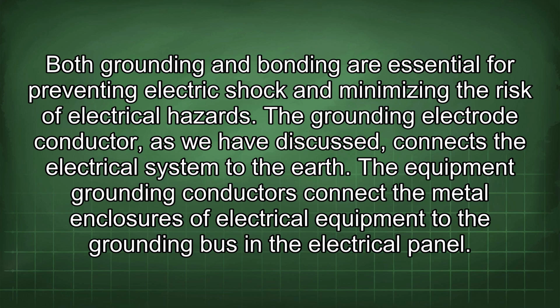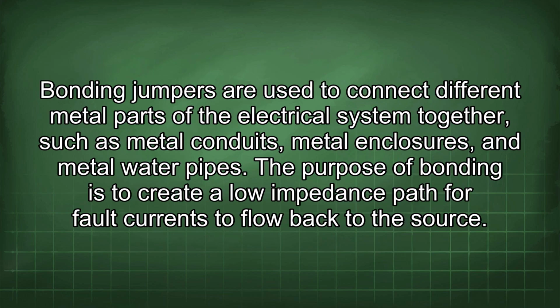The grounding electrode conductor, as we have discussed, connects the electrical system to the earth. The equipment grounding conductors connect the metal enclosures of electrical equipment to the grounding bus in the electrical panel. Bonding jumpers are used to connect different metal parts of the electrical system together, such as metal conduits, metal enclosures, and metal water pipes.